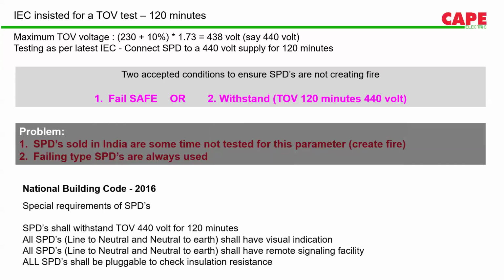But unfortunately, in India most manufacturers are not educating clients about this TOV parameter. Sometimes they are not even aware of it. Our National Building Code of India 2016 clearly states that SPDs sold in India shall have TOV immunity. Additionally, NBC says that all SPDs sold in India shall have indication line to neutral or line to earth in case of 4+0 connection, as well as neutral to earth, because the neutral to earth plug is as important as the line to neutral plugs. So all SPDs shall be pluggable and shall have remote signaling or failure indication in all the plugs.